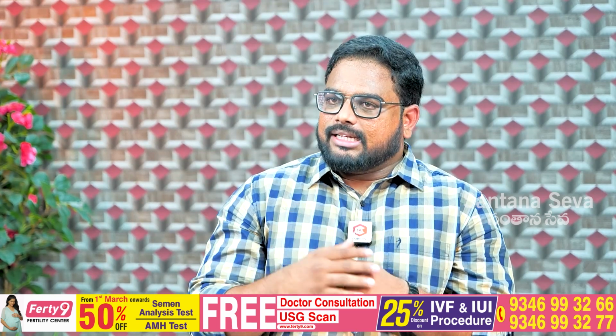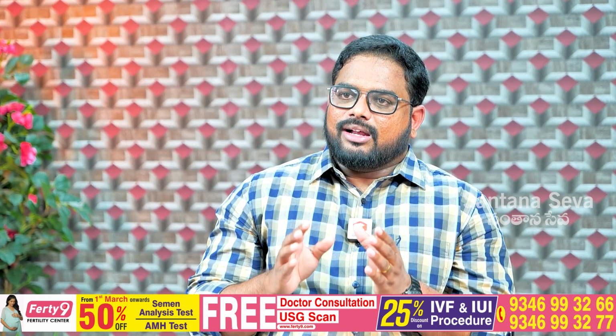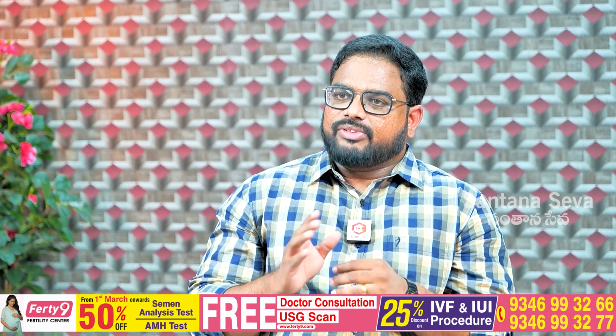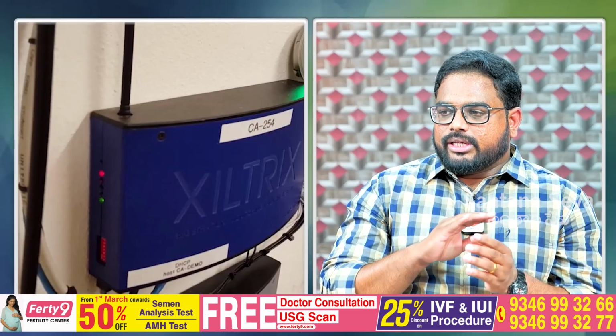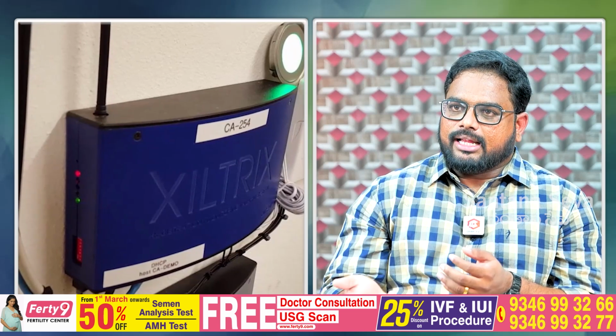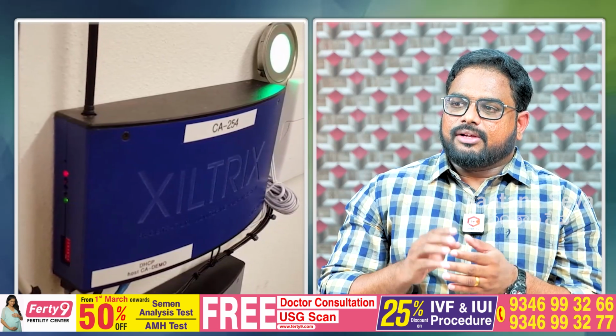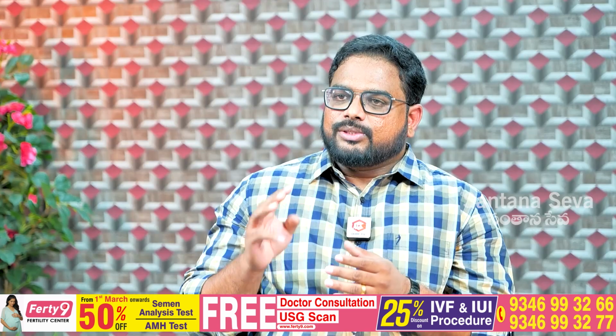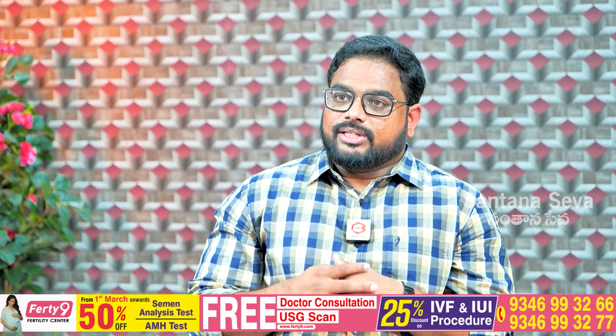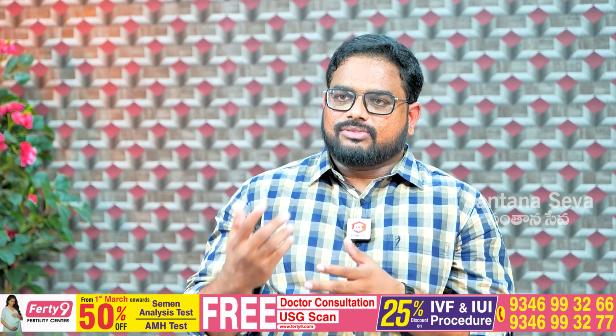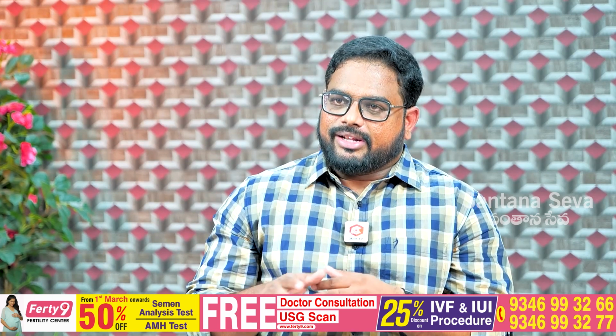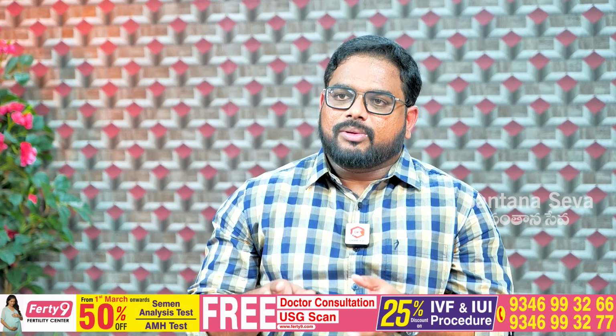For that we have Xiltrix. This is one of the advanced systems we are using right now in India. It monitors 24/7. If there is a power surge or any power failure, we'll get a notification. We have 3 layers, so 3 persons will be notified. If there is any problem, one of us will assist and rectify it, so that no problem will happen.